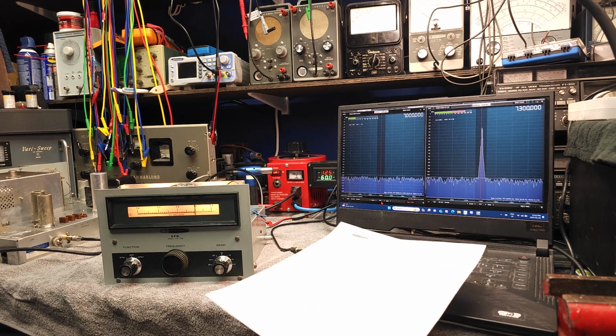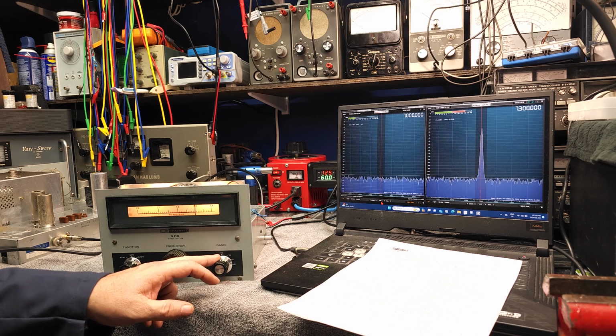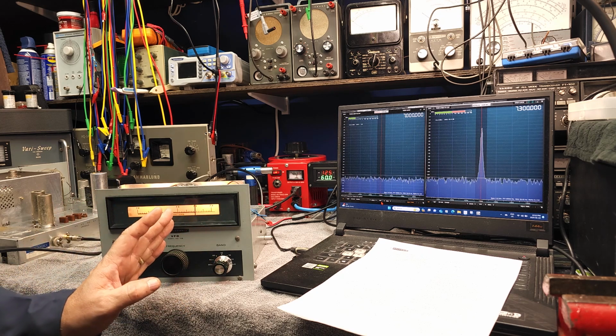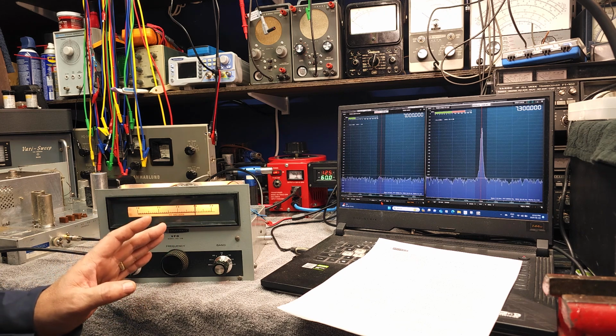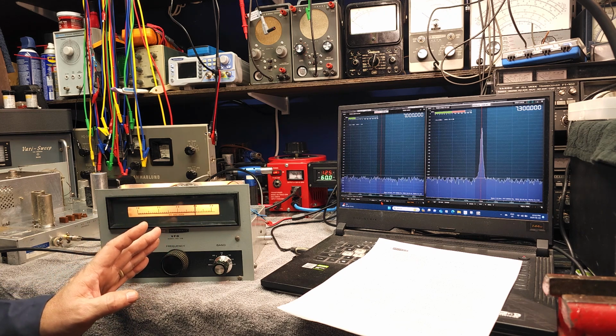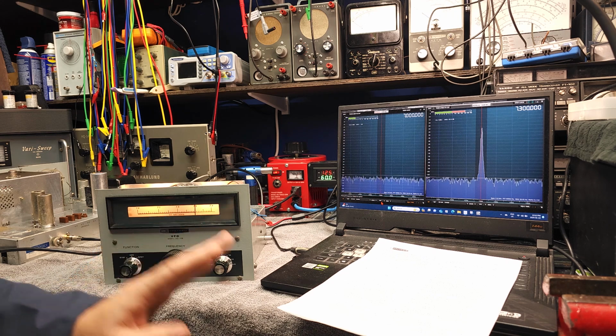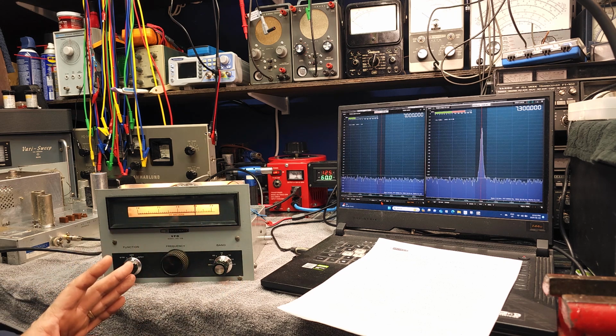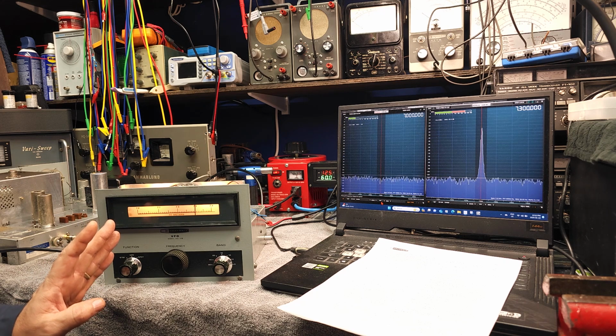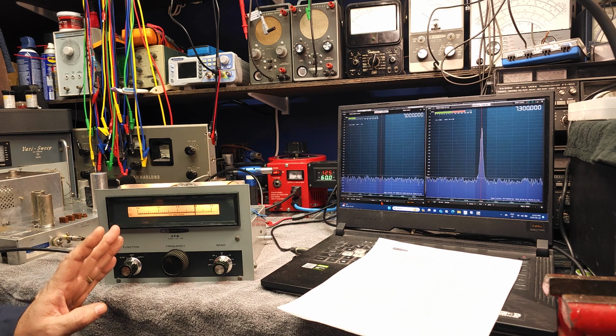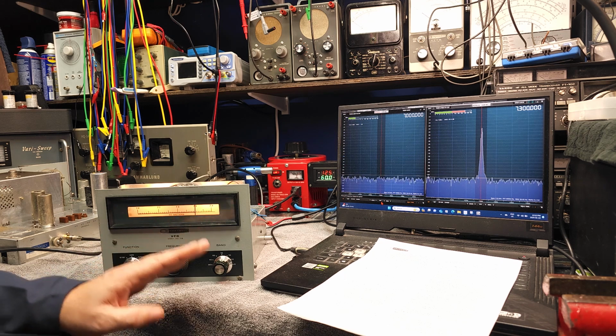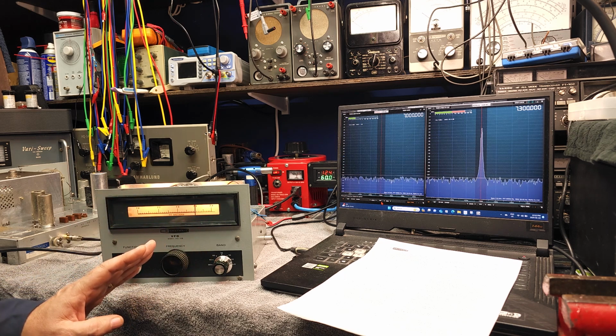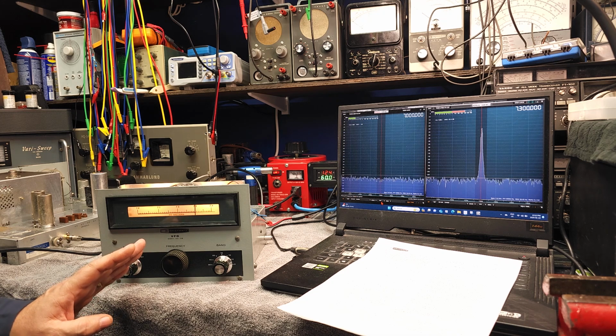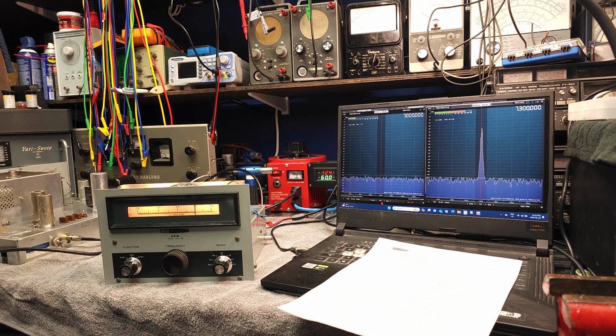So we'll get set up and go to 20 to see if it's on frequency. But honestly, if 20 is not on, there's not a lot you can do about it, because if you adjust 20 - which the manual doesn't want you to do - then 7 goes out. They want you to align it on 7, and hopefully 20, 15, and 10 should be on frequency. So let's go through them and see how accurate it is. 40's on, we know that, it's working good. So let's look at 20 - I'll set up for 20 and be right back.